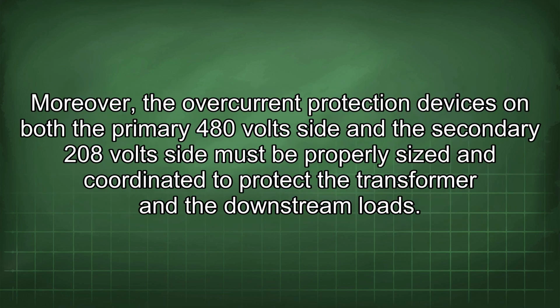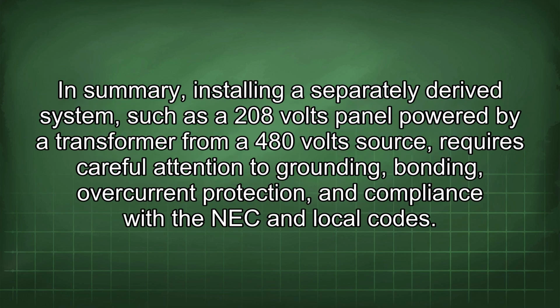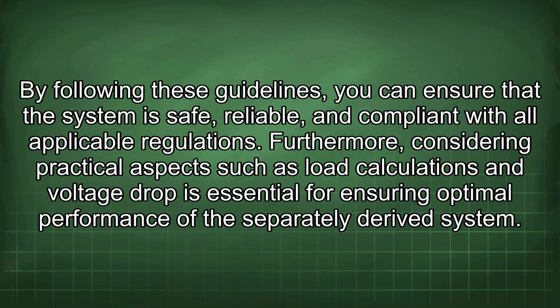Moreover, the overcurrent protection devices on both the primary 480 volt side and the secondary 208 volt side must be properly sized and coordinated to protect the transformer and the downstream loads. In summary, installing a separately derived system, such as a 208 volts panel powered by a transformer from a 480 volt source, requires careful attention to grounding, bonding, overcurrent protection, and compliance with the NEC and local codes. By following these guidelines, you can ensure that the system is safe, reliable, and compliant with all applicable regulations.